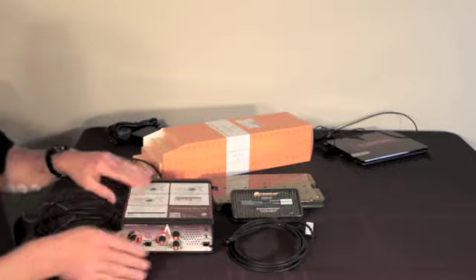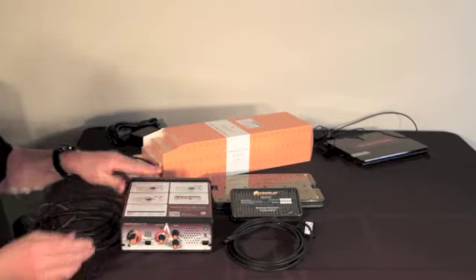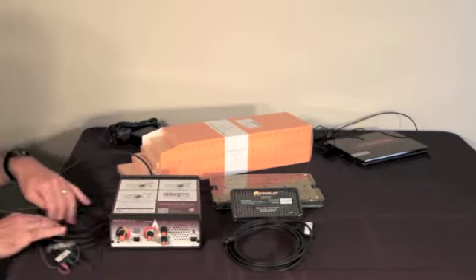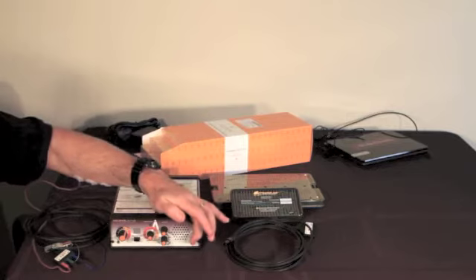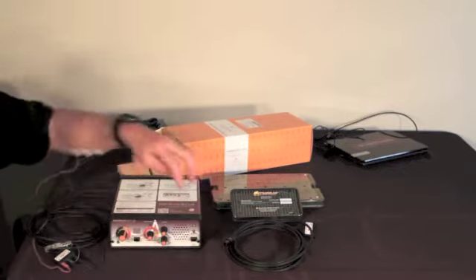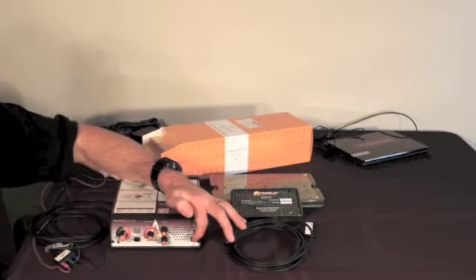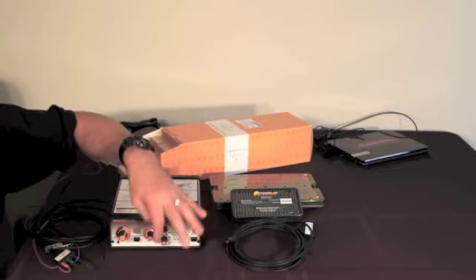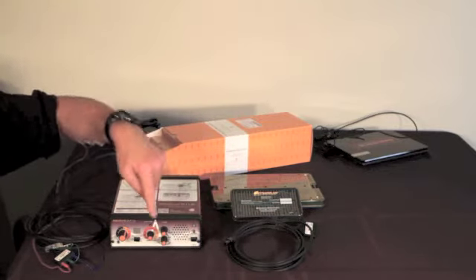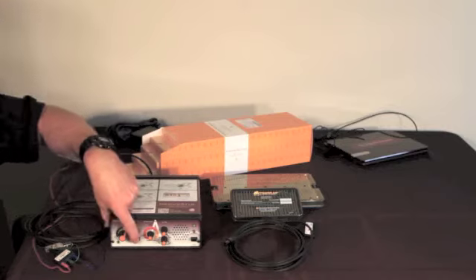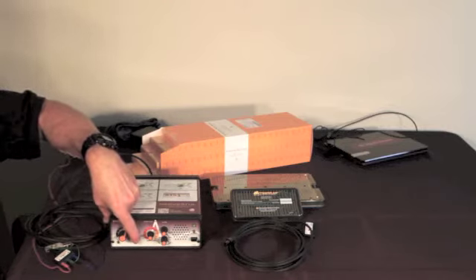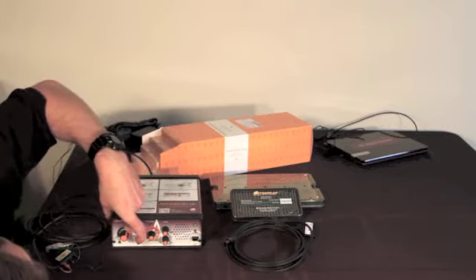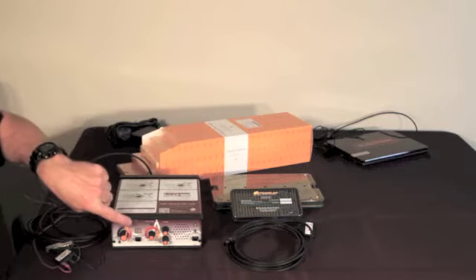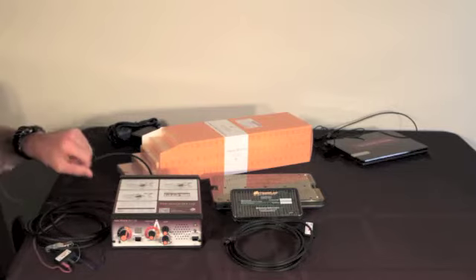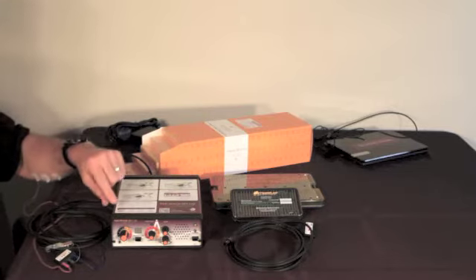At this point, the sterile field hasn't really been set up around the patient, and the patient hasn't been prepped for sterility. And so you're able to test this connection, and if necessary, go back and reapply electrodes. So once I've turned on the machine and I have my signal amplification at 100%, I hold this test button for at least 6 seconds. And then I watch, when I release, the 3 readings that appear. In this case, I had 10, 16, and 7.8.